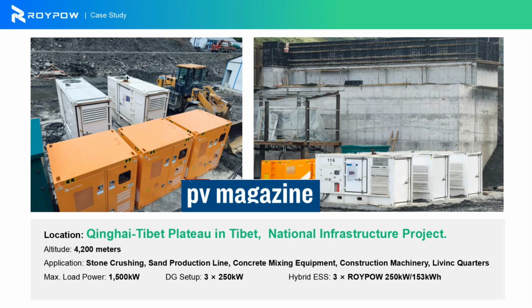The maximum load power needed for this project is 1,500 kilowatt. If they used a diesel generator setup with 250 kilowatt units, they'd need like 6 or even 7. So we provided a solution with diesel generators 3 times 250 kilowatt, together with our hybrid ESS 3 times 250 kilowatt, to support the load power.